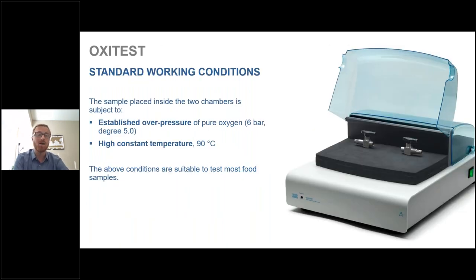Regarding OXITEST standard working conditions: the sample is placed inside two chambers and is subjected to an established overpressure of pure oxygen, typically around 6 bar, and a high constant temperature, typically around 90 degrees Celsius. The instrument can go up to 120 degrees Celsius and 6 bar, but these standard conditions are suitable for most food samples.